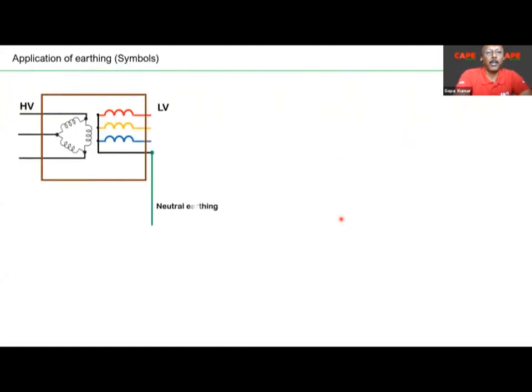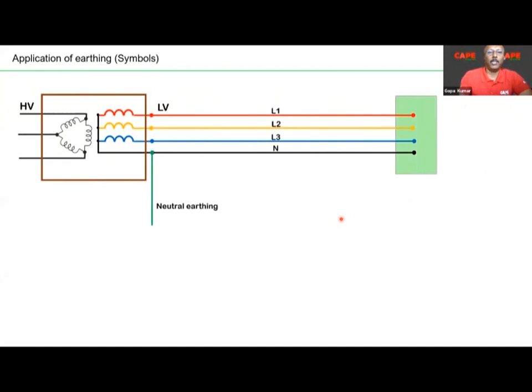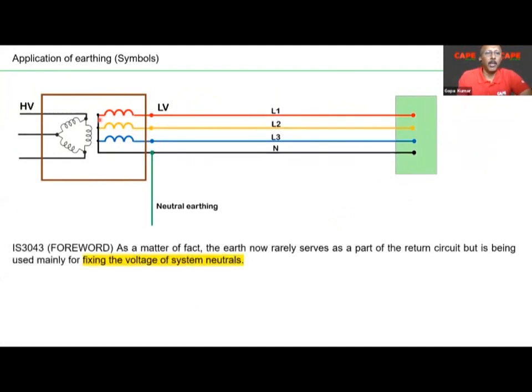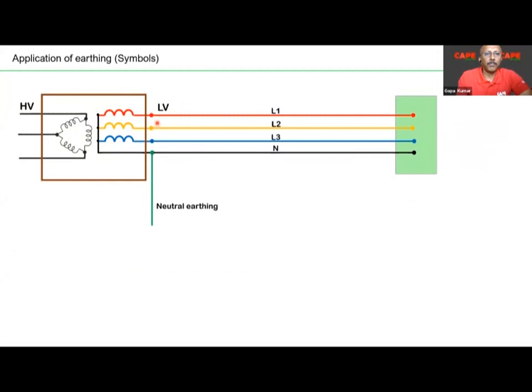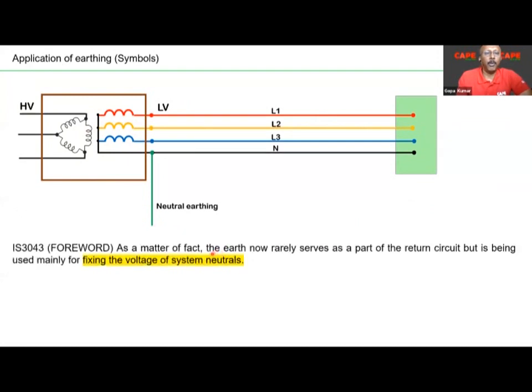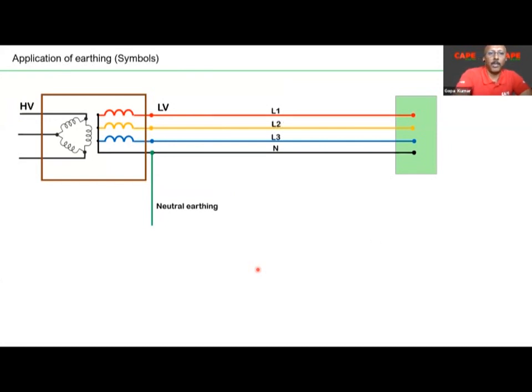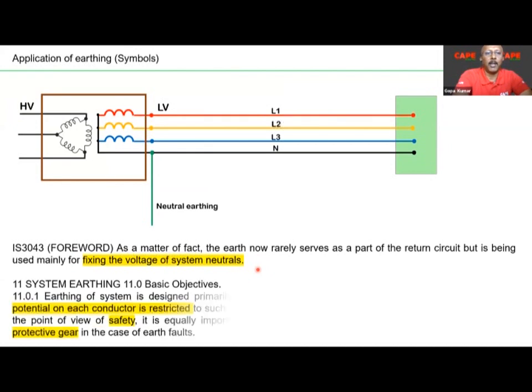Now, imagine a transformer neutral. I'm just showing you a picture of a transformer. The three phases go to the equipment. You have the neutral, and the neutral is earthed. If you look at the foreword of IS 3043, what is written is that, as a matter of fact, the earth now rarely serves as part of the return circuit, but it is mainly used for fixing the voltage of system neutrals. So earthing is used for fixing the voltage of the neutral. That means it is a functional requirement.